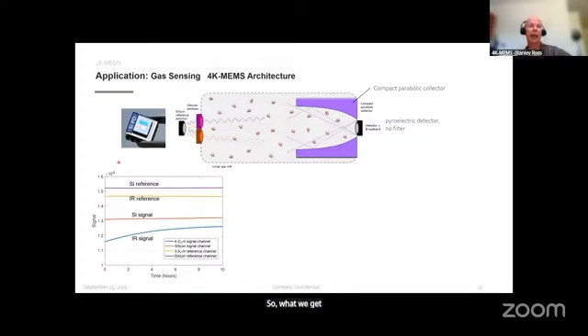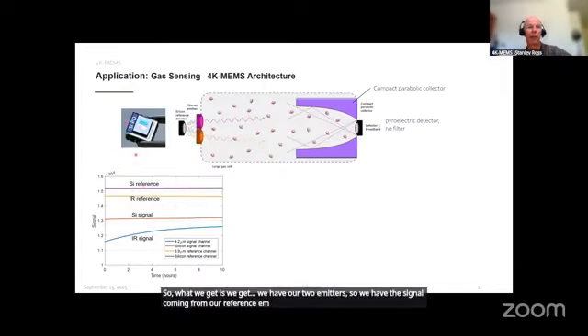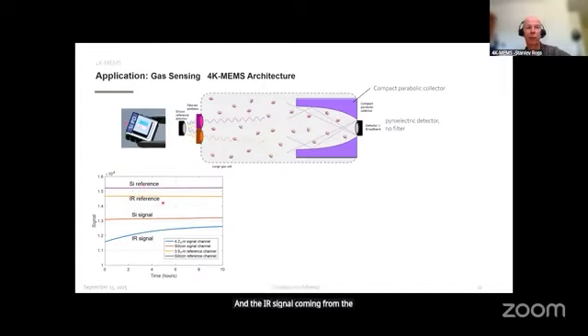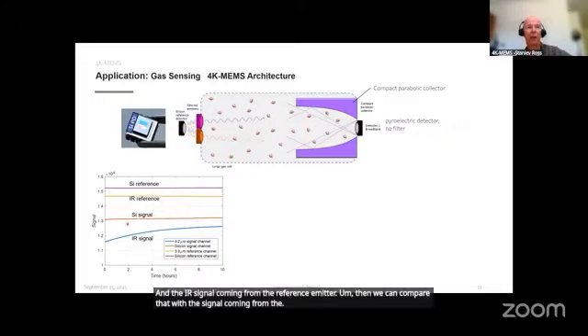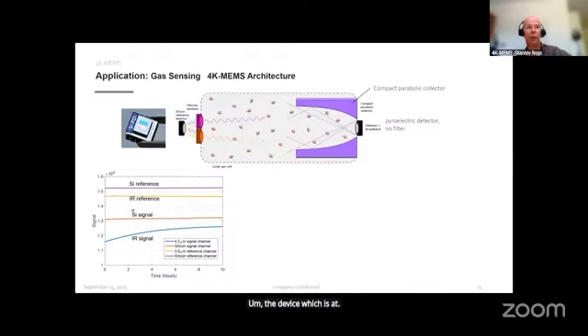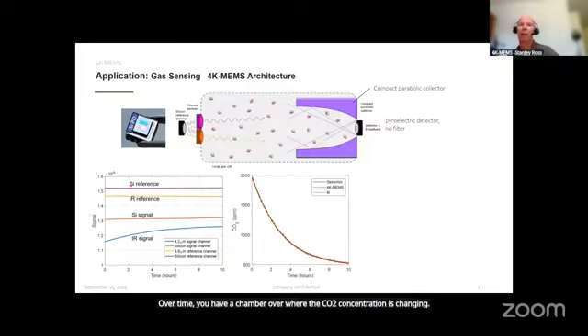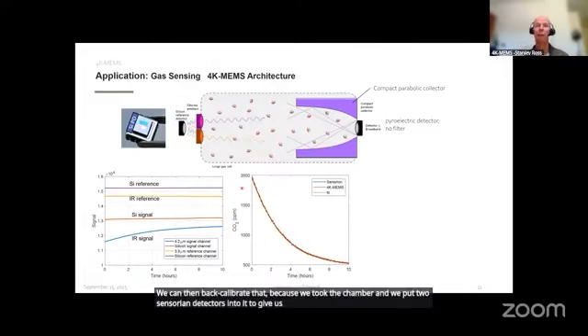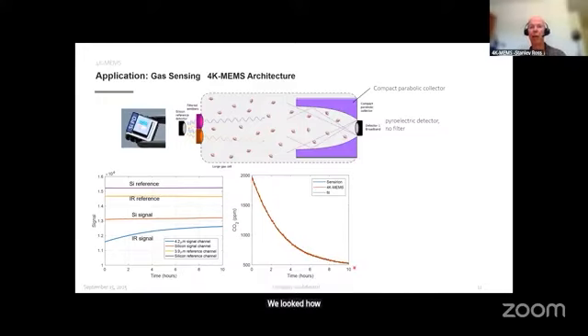So what we get is we have our 2 emitters. We have the signal coming from a reference emitter measured by silicon and the IR signal coming from the reference emitter. And then we can compare that with the signal coming from the device, which is at 4.2 microns. And so what we see here, over time, we have a chamber where the CO2 concentration is changing. We can back calibrate that because we took the chamber and we put 2 Sensirion detectors into it to give us a background signal. We looked at how the CO2 changes in time. We can use that as a calibration curve. We can compare it with our emitters, and then we can look at the residuals.